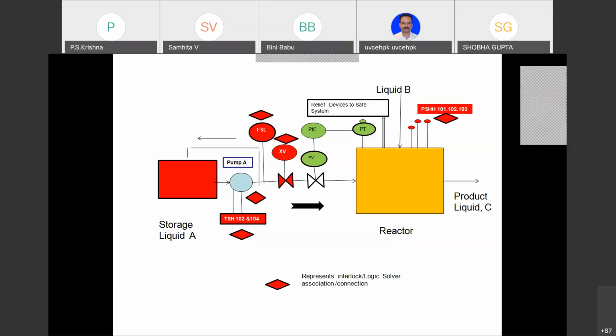So we gave this 2 out of 3 voting system. That means this has to say yes, this has to say yes, and only then will it happen. Why 2? Why not 1 only? Because there is a study called voting system, which I'm going to show you in the end. One day, the first one cleverly told it, please shut down the plant. That was spurious. It was not called for.